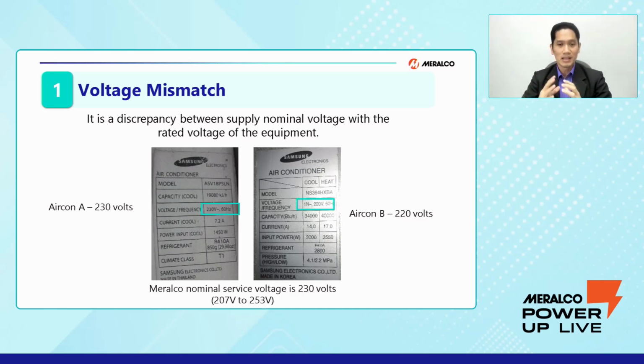But we have to take note that Meralco's service voltage is 230 volts, with an allowable variation of 207 volts to 253 volts. But we also have to mind that sometimes the mismatch is not just in the rating of the equipment, but also in the setting of our voltage protection relay. There are instances when we receive complaints, but upon checking or investigating, the voltage relay of our customers is set outside the allowable voltage variation as allowed in the Philippine Distribution Code. Thus, it results in nuisance tripping.